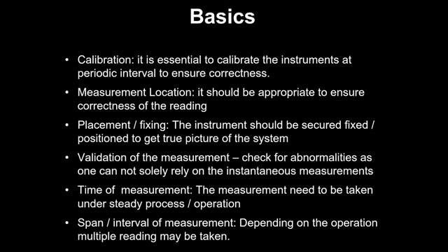If it is varying from 200 to 220, now for the pump analysis or a chiller analysis or cooling tower analysis, what values do we take? So there are two options. One option is you take some 8, 9 or 10 readings at 5 minute or 1 minute intervals and find the average. Another method, which we normally use: our flow meter has a totalizer. So you activate the totalizer function, do it for 10 minutes and then average out, so that the calculations are based on the average value. So this again needs to be assessed.